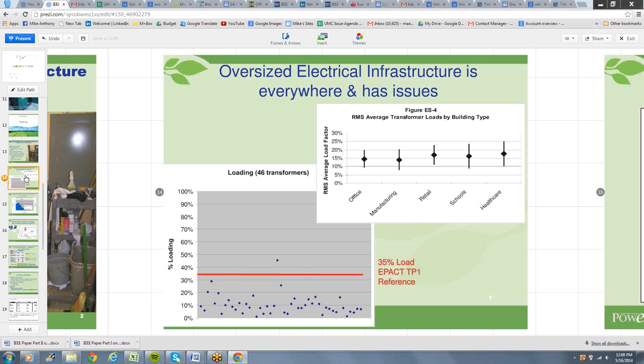So, you would expect, at first blush, that they would all be quite different, but that in fact is not the case. We've gone out in the field ourselves. We do a lot of work in the field replacing transformers, and as you can see on the bottom left, our findings are really quite similar, as you can see from the scatter plot. And that's important because the legislation for minimum legal efficiency for a transformer references 35% load, and as you can see, we're far below that.